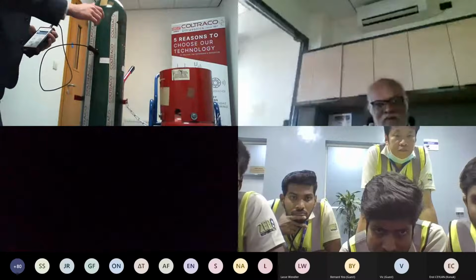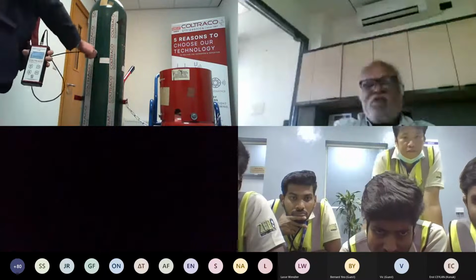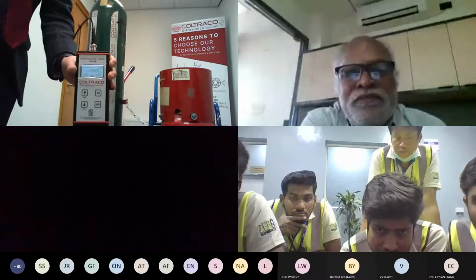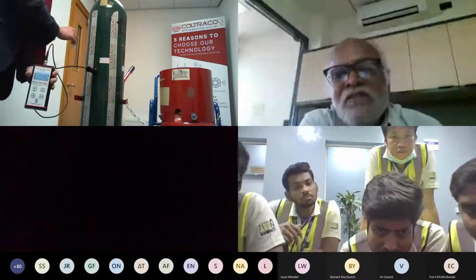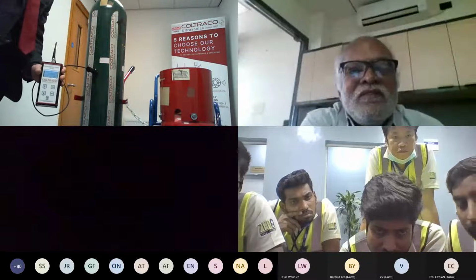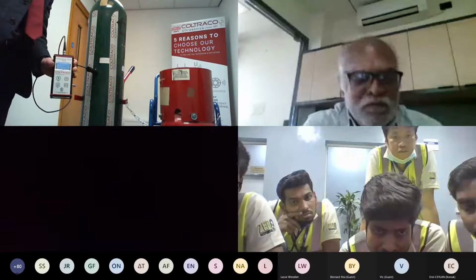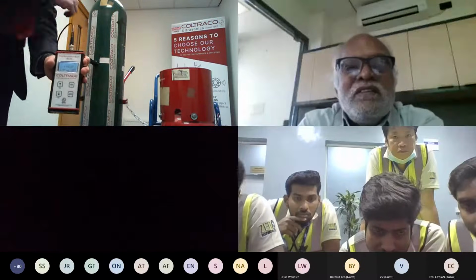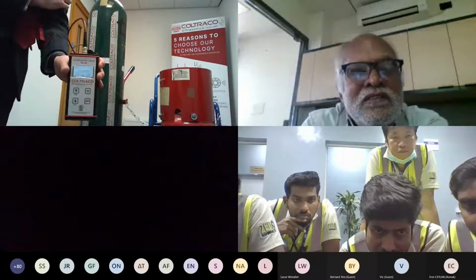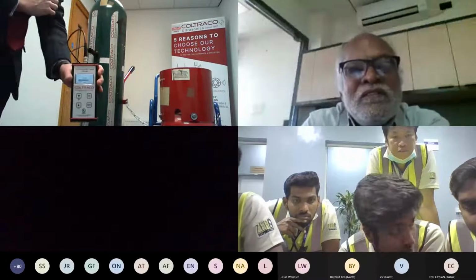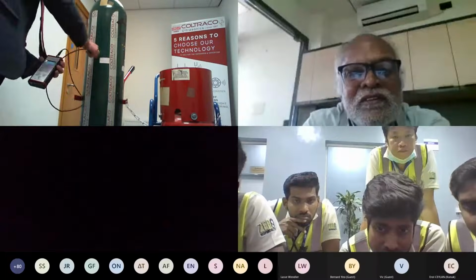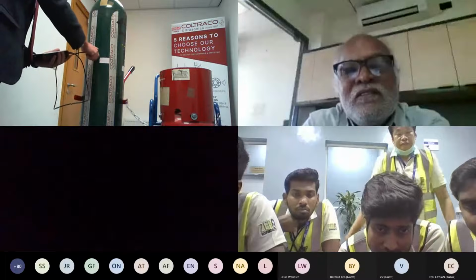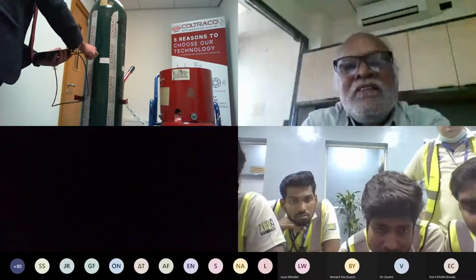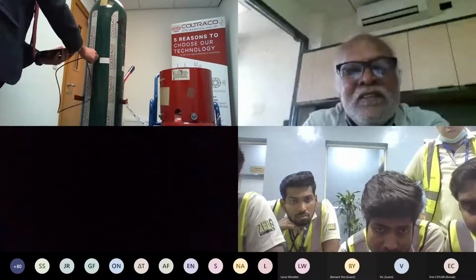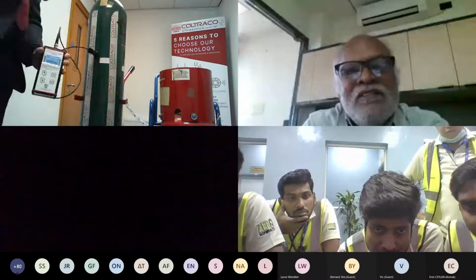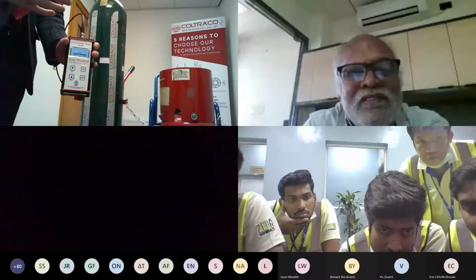So now, when I move the sensor down, you can still see it's reading gas. But now, as you can see, it's reading liquid when I've passed a liquid point. So I now move back up the cylinder in small steps until I find the exact point where it switches between gas and liquid. So still in liquid. Still in liquid. And now in gas. So move down just a fine step, just to find the exact point. Okay, about here. This is the exact point where it's switching between gas and liquid.